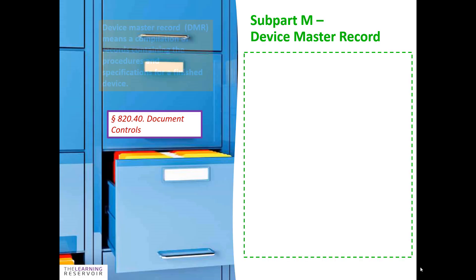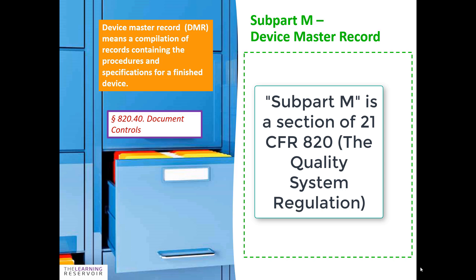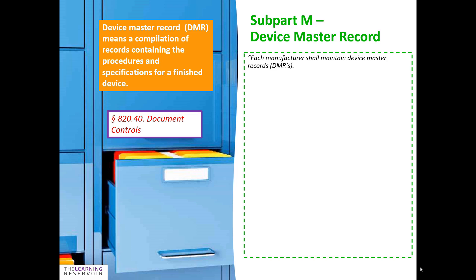Within Part M it states that you have to have a device master record. A device master record means the gathering of all the records containing the procedures and specifications for a finished device. In the regulation it states that each manufacturer shall maintain device master records, and each manufacturer shall ensure that each device master record is prepared and approved in accordance with §820.40.